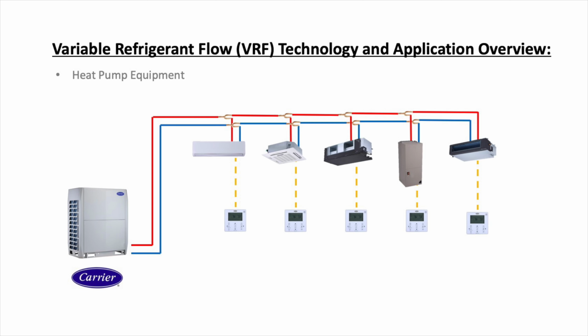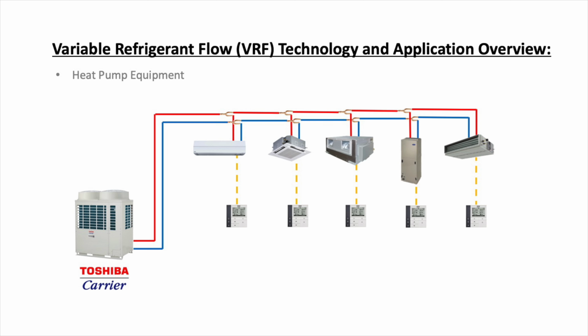Here's a basic layout piping schematic of a heat pump system. This one is a Carrier system. So you have your 2 refrigerant lines coming out of the outdoor unit, Y branching into each indoor unit, and each indoor unit is connected to its own remote controller. The Toshiba Carrier is very similar. You've got your 2 refrigerant pipes coming from the outdoor unit, Y branching into each indoor unit, and each indoor unit has its own remote controller.